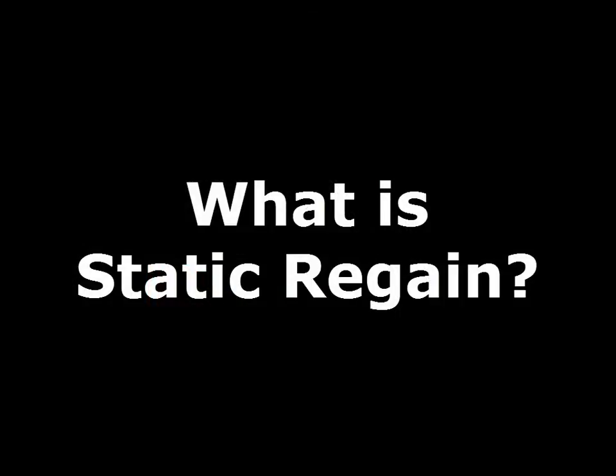I'm Jenny Abney-Civy, and today we're going to answer the question, what is static regain? Static regain is exactly what it sounds like, a way of regaining static pressure in an HVAC system. Hopefully you remember from one of the early podcasts that total pressure equals velocity pressure plus static pressure.